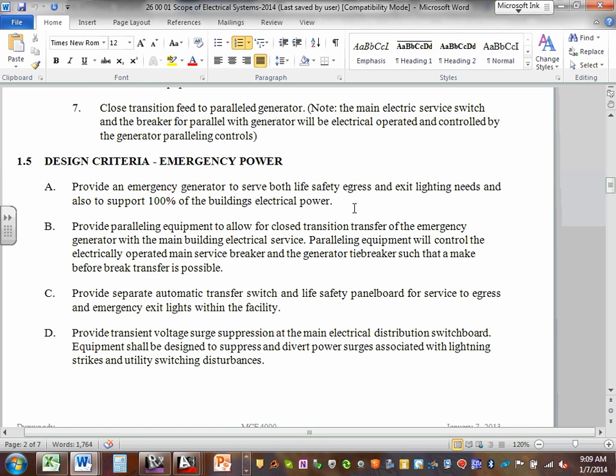There's going to be paralleling equipment, and it's going to allow for closed transition transfer to emergency generator, which means when you go from utility to generator, you're not going to see a power blip. It's going to be all seamless. You turn the generator on, sync the two sources, move the load over to the generator without a power outage. We are going to be providing separate automatic transfer switches for the life safety panel board. Even though the generator is going to be feeding the entire building, we need to keep the building and the exit egress life safety stuff separate. There are some coordination things that we need to do differently, and that's the reason why we separate them.